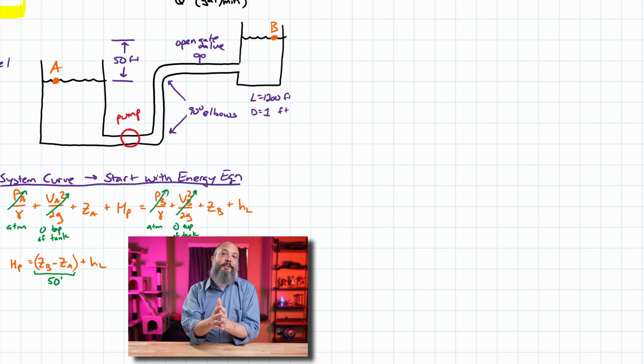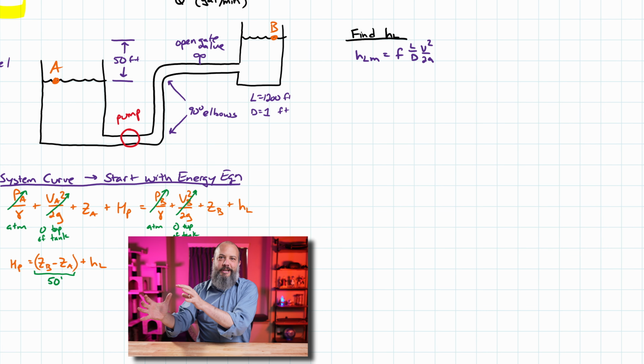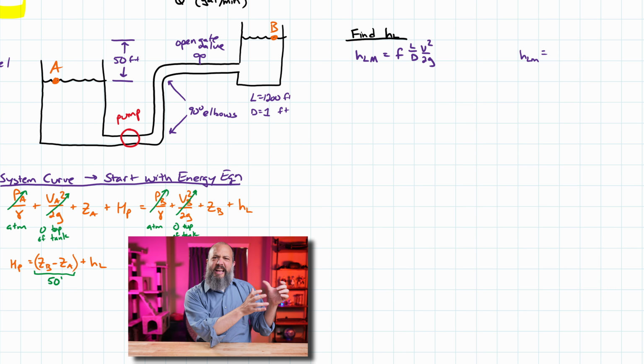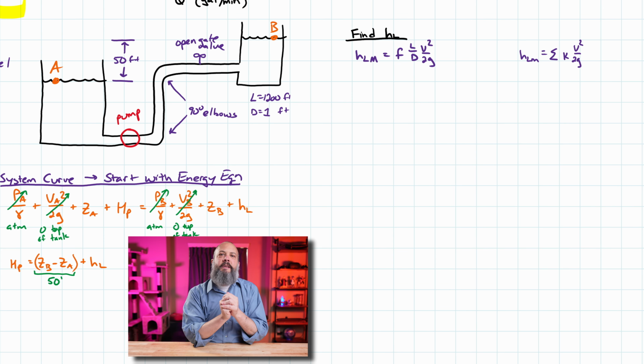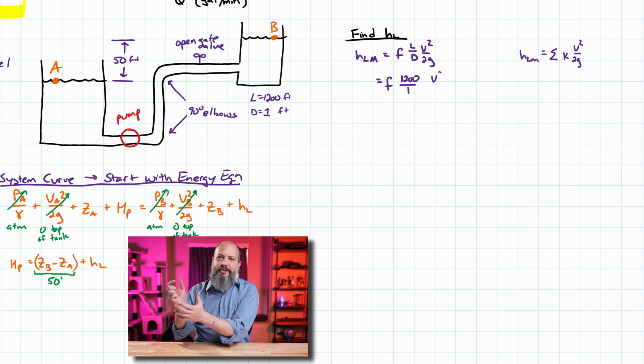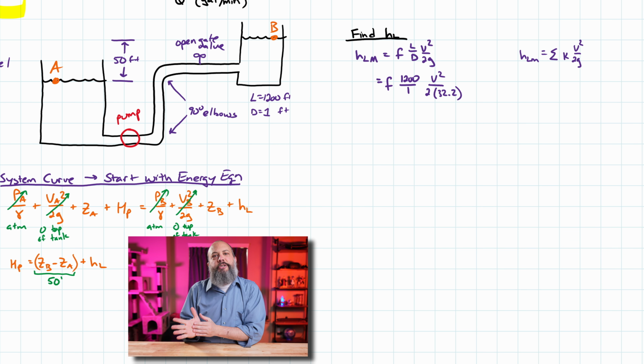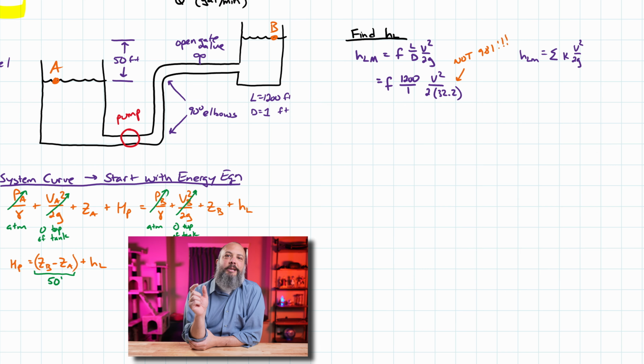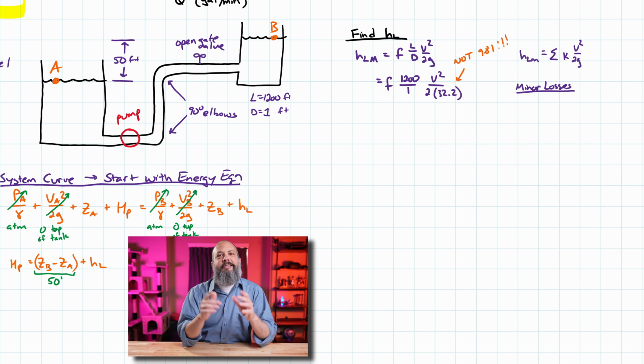So head loss is going to be divided into major losses for friction and minor losses for all of the extra components in the system. So for the friction, I'll use the Darcy-Weisbach equation, where this f is gonna come from the Moody diagram. So f L over D, V squared over 2g. The length is 1,200 feet and the diameter, I'm gonna do 1 foot to make sure the units cancel out, not 12 inches. And the biggest, easiest thing for a student to mess up is that g is 32.2 when we're using feet units, right? Not 9.81, which is the metric system.